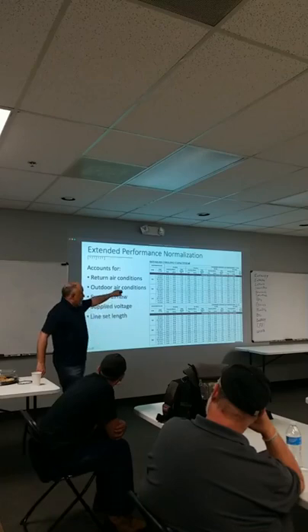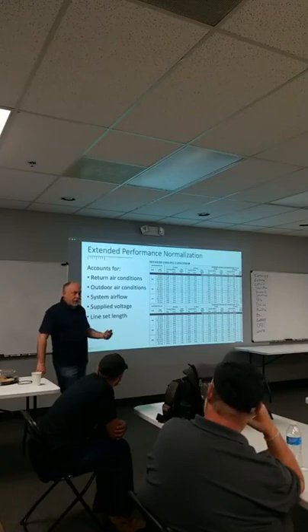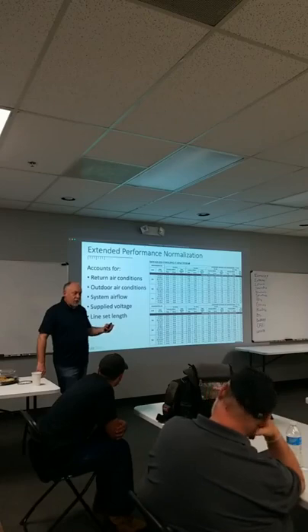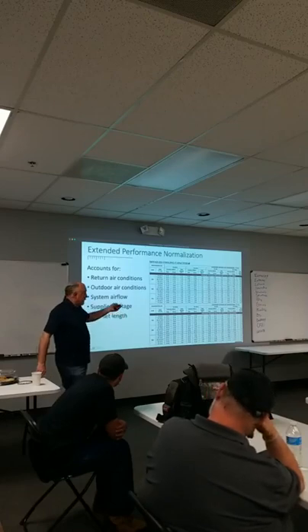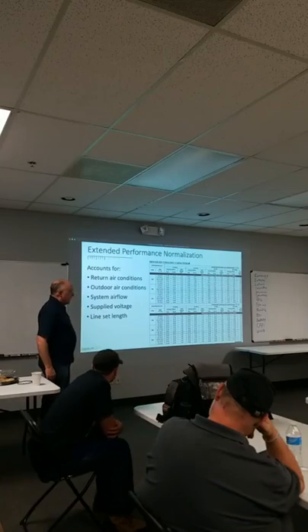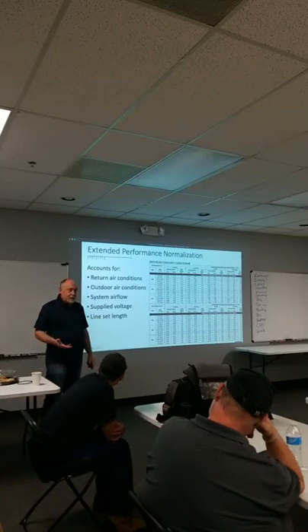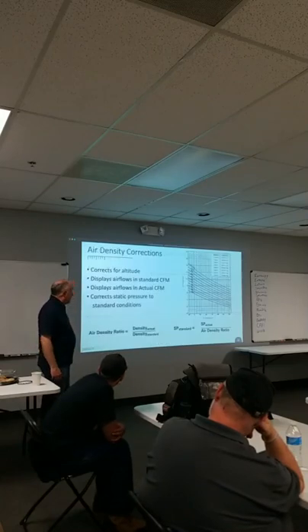That equipment's engineered for 400 CFM a ton. If you run it at 350, you're gonna have lower capacity, right? So line set length, your voltage, your airflow selection, all play into and affect your calculations. And again, because we have a computer that can calculate this stuff, we do, right?